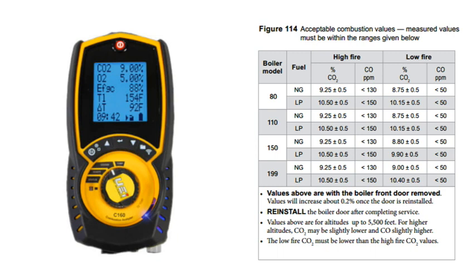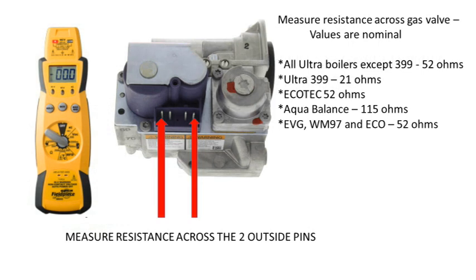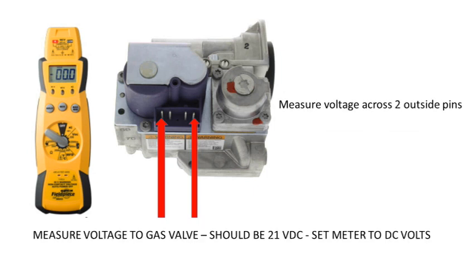Have combustion settings been adjusted? Confirm CO2 and CO are correct. Are all the gas train gaskets tight? Check gaskets for airtight seal. Do the windings of the gas valve show the correct resistance? Is the gas valve receiving the proper voltage?